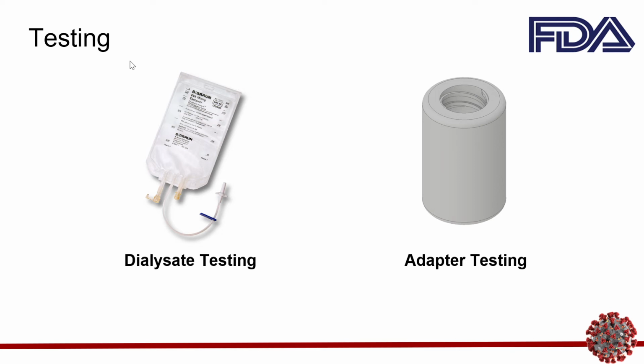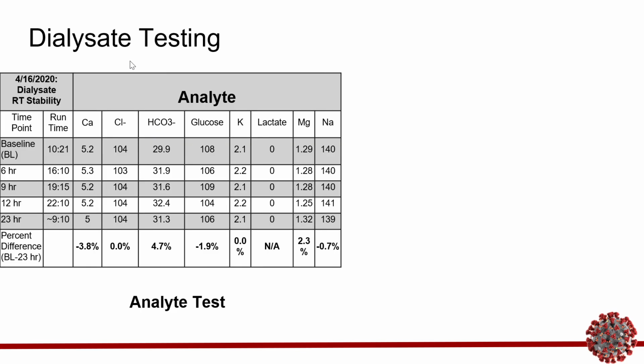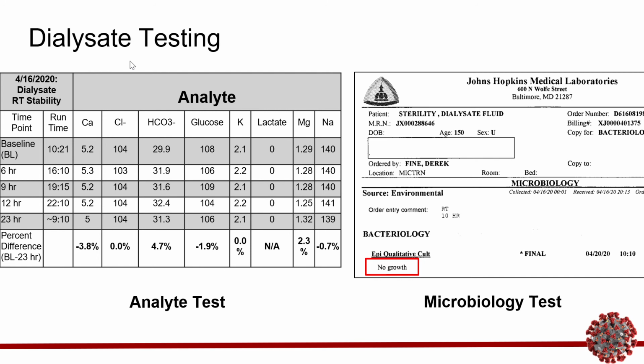We performed 2 tests on the dialysate and 3 tests on the adapter. For the dialysate, we performed chemical testing to see if the concentration of analytes in the dialysate changed over time. Our results were successful, and we found that all analytes remained in safe and stable conditions over a 23-hour period. Next, we performed a 2-day microbiology test to determine if any bacteria or endotoxins grew in the dialysate. The results came back with no growth, showing that the dialysate could be collected without any contamination.